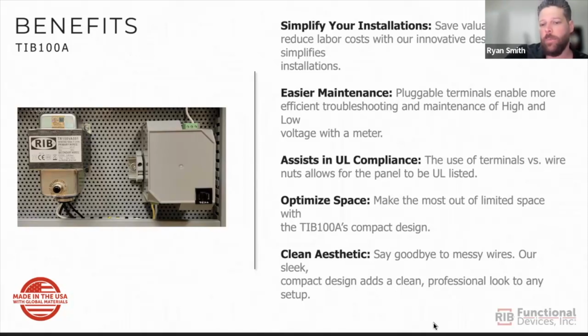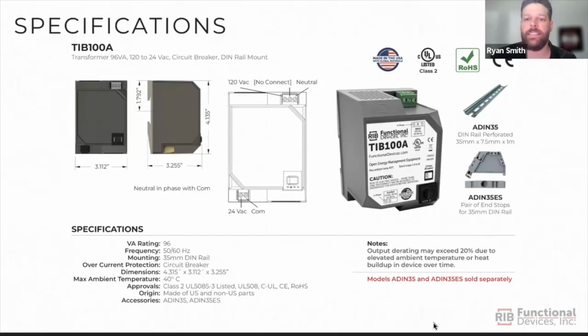Maintenance on the TIB is made efficient with the pluggable terminals, allowing for easy metering of primary and secondary terminals. The use of terminals also assists in UL compliance by removing the need for wire nuts in the control panel. The TIB optimizes space in your panel and removes messy wires, creating a clean aesthetic in your panel projects. The TIB contains a 96 VA transformer that lowers the voltage from 120 volts AC to 24 volts AC. There's a built-in 4-amp breaker to protect the device from downstream wiring issues. Functional Devices also offers accessories like the DIN rail end stops and the actual DIN rail to complete your application of the TIB into your control panel.